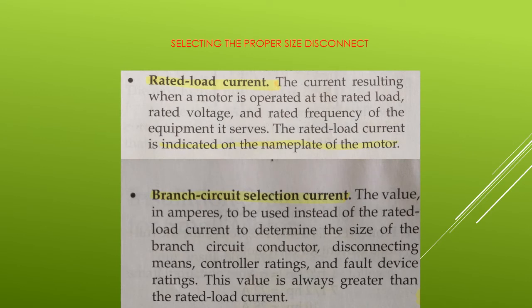Selecting proper size disconnect. Before discussing the proper disconnect and sizing, we must define a few terms. Rated load current is the first term: the current resulting when a motor is operated at the rated load, rated voltage, and rated frequency of the equipment it serves. The rated load current is indicated on the nameplate of the motor.